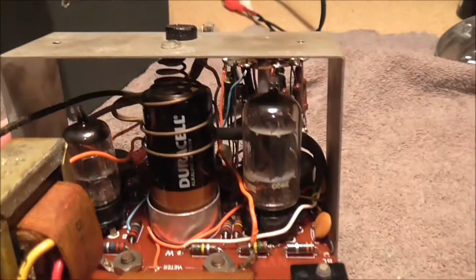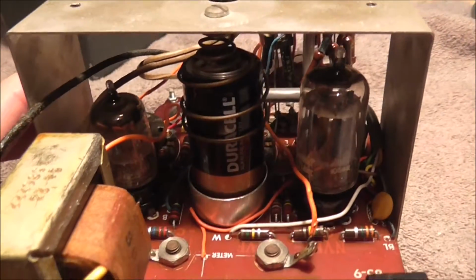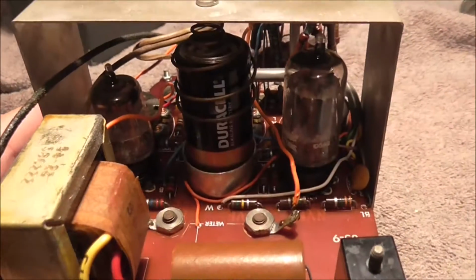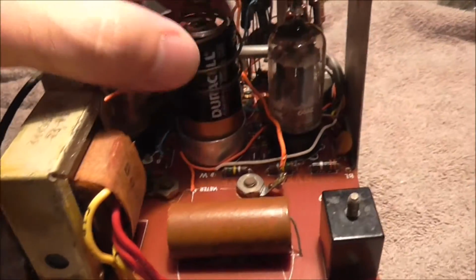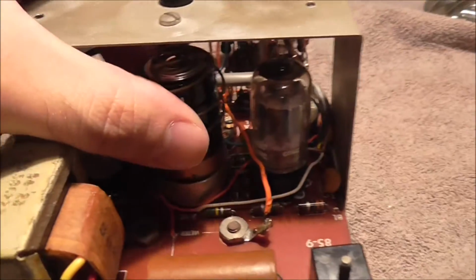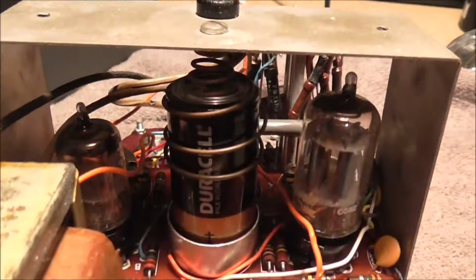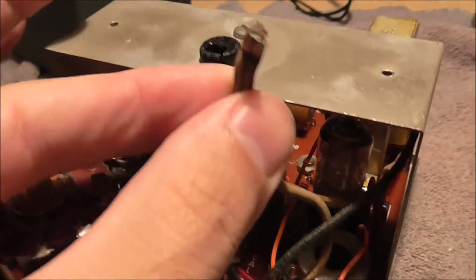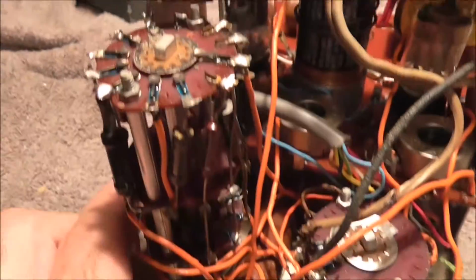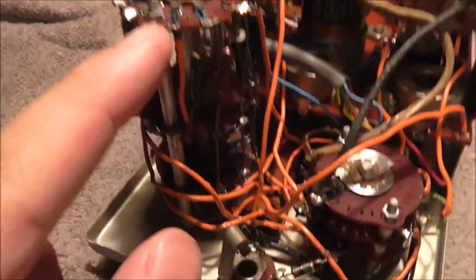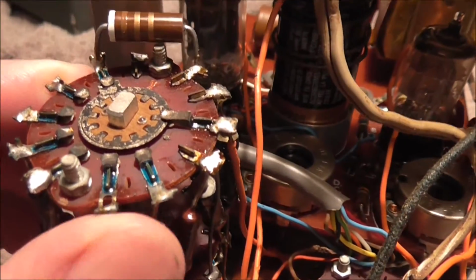So you can see the 2 vacuum tubes there. I believe one is basically used as some kind of regulator and the other one actually drives the meter, or the measurement per se. There's a battery in here. This has probably been replaced at some point. The battery is not leaking or anything. It's got a transformer here. You can see the wires were just cut right there. And here's where the power cord went out. It's right there. There's the main selector switch here, which I may want to run some contact cleaner on to try and fix that.